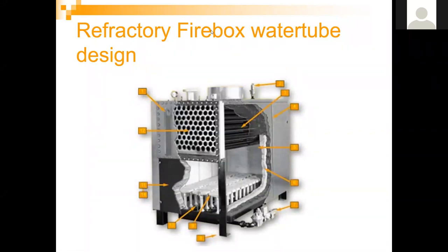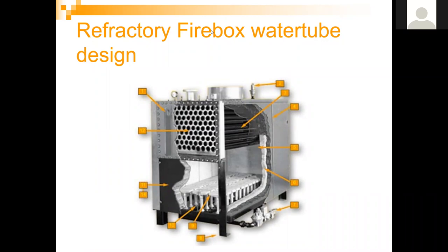Addressing a question about room volume calculation: it's not just the volume of the tubes — they calculate the entire pressure vessel volume. It's more than just the tubes; it's the entire pressure vessel. You don't have to include the burner volume or external insulation components, but you do calculate the entire pressure vessel when determining that 12 or 16 times the room volume requirement.